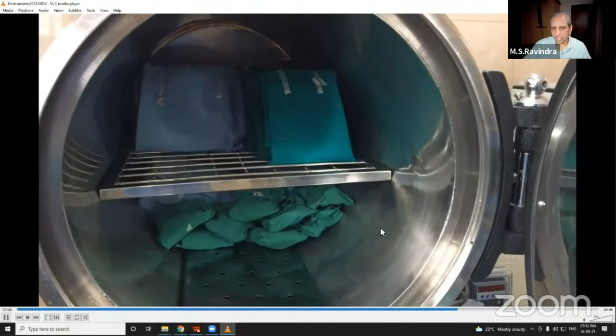And these autoclaves have to be validated by a third party. The supplier should not validate them. Third party person runs the cycle, validates them, and titrates the number of vacuum cycles and heat cycles. Our autoclave has got 4 cycles of depurging. So that's how, and it has to be periodically validated once in 6 months.